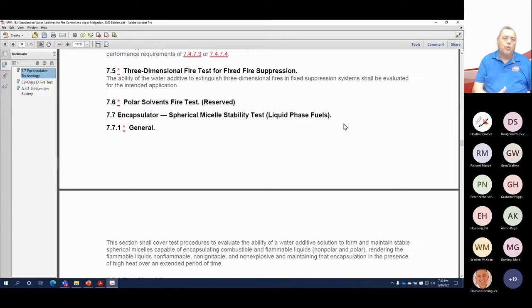When you run, say, a UL 162 test, a lot of people think that's a fire test, but if you take a step back and look at it 180 degrees, it's really a bubble or film integrity test. If I have really crappy bubbles, I'm not going to put the fire out or control it in 1 minute, and I won't extinguish it in 5 minutes. If I have average bubbles, I can control the fire in 1 minute and extinguish it within 5 minutes, but I won't pass the burn-back resistance test.